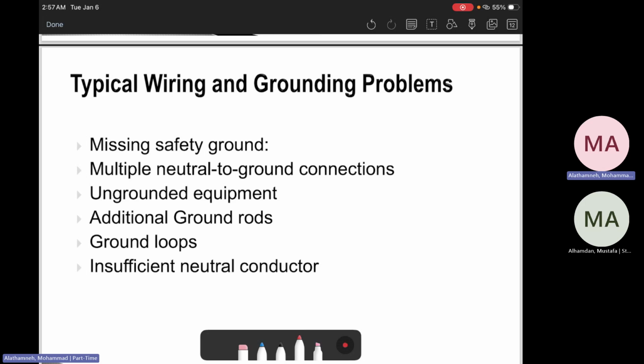However, in the old days or old buildings, you can see the neutral wire is very thin. So basically what's happening there, since it's very thin, we have some harmonics that come from electronics, called the tripling harmonics, or the third harmonics. It can be a significant value, so huge currents can flow in there, while this small thickness of neutral makes it incapable of handling that huge value of neutral current coming from the triplen harmonics, which creates a problem and makes it overheat.